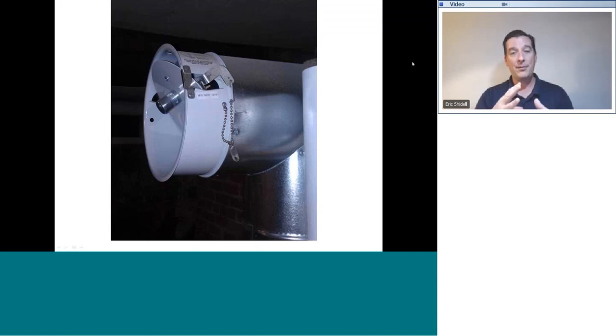So to prevent all of those bad things from happening, a barometric damper is installed in the flue, and it's usually installed in the T. So that as the flue pulls harder when the wind blows, it pulls the little damper open. The damper has just got a weight on it. And when the flue pulls harder, it pulls air in from the room, divorcing the draw of the flue from the draw of the furnace or boiler. The furnace or boiler, however, is still under negative pressure. Let's explain that for a second.